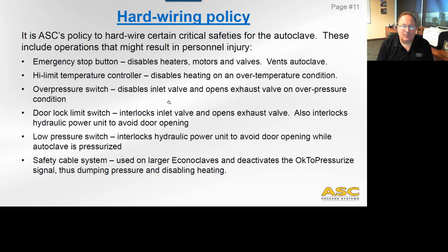And the low pressure switch, another important one, is basically a very low pressure switch that operates at about a half a PSI, and it is interlocked with the hydraulic power unit to make sure that we cannot open the door if there's pressure in the autoclave. So that is a very important one. Without that, we would likely be opening doors under pressure, which is not good. And lastly, the safety cable system, which is basically the person-in-the-autoclave cable, used on larger autoclaves and deactivates the OK to pressurize signal, thus dumping pressure and disabling heat.